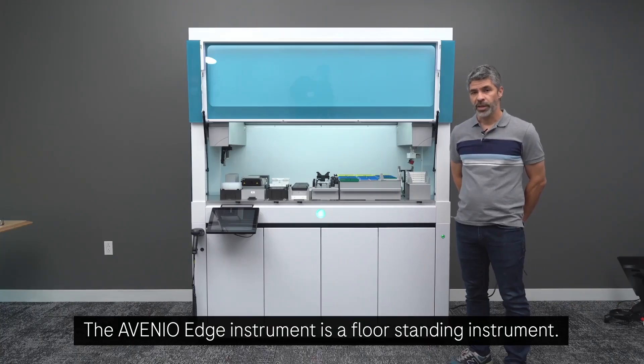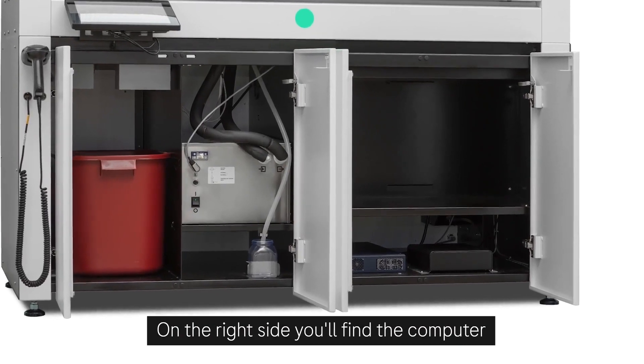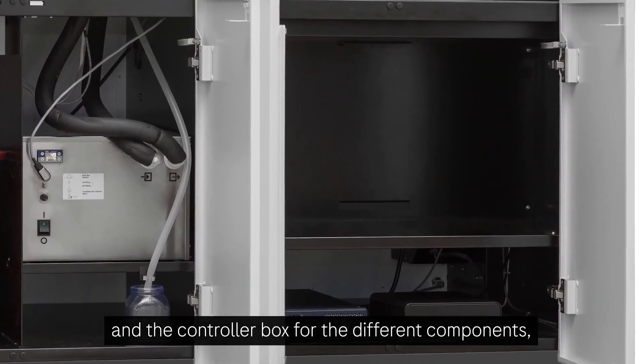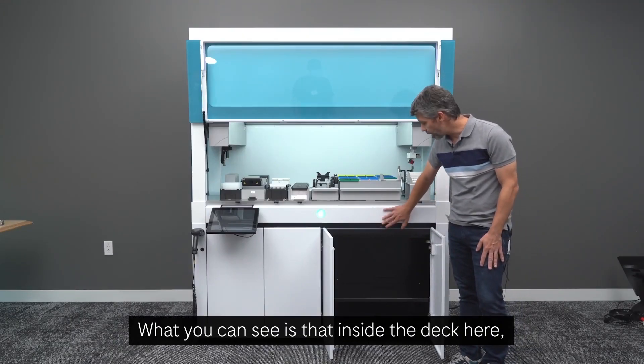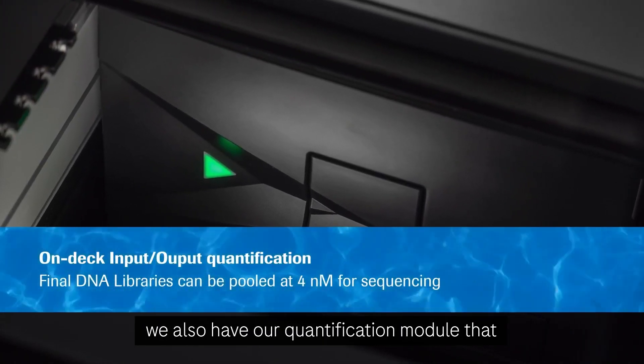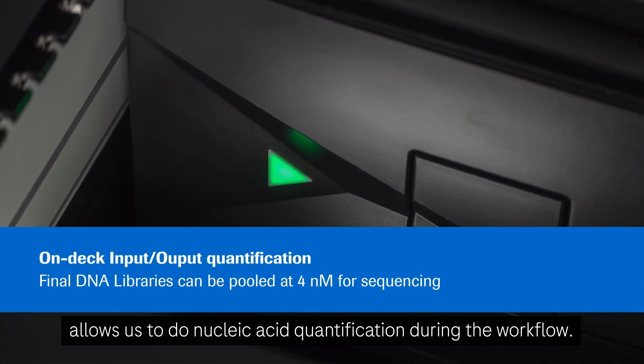The AVENIO Edge instrument is a floor standing instrument. On the right side, you'll find the computer and the controller box for the different components, and also some storage area. What you can see is that inside the deck here, we also have our quantification module that allows us to do nucleic acid quantification during the workflow.